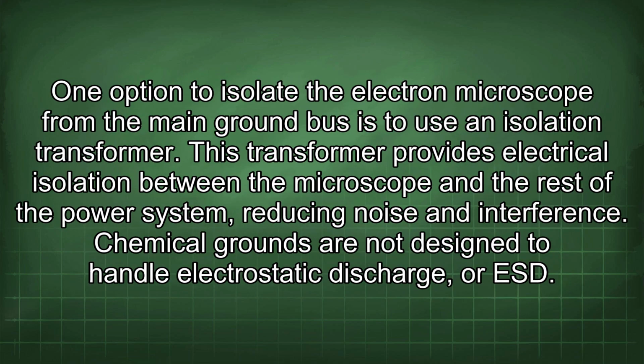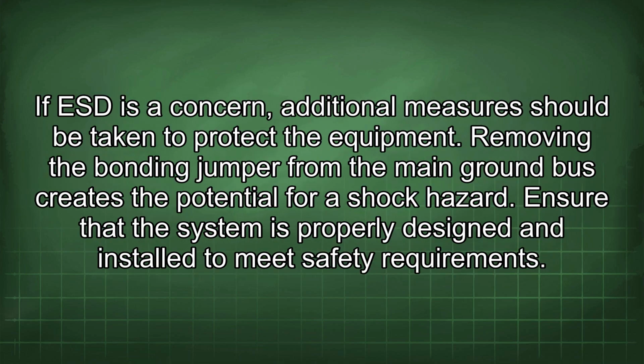One option to isolate the electron microscope from the main ground bus is to use an isolation transformer. This transformer provides electrical isolation between the microscope and the rest of the power system, reducing noise and interference. Chemical grounds are not designed to handle electrostatic discharge, or ESD. If ESD is a concern, additional measures should be taken to protect the equipment.